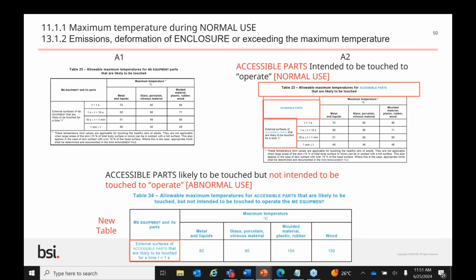Maintenance Team 30, the Overheating, Fire Protection, and Additional Hazards Maintenance Team, updated Table 23. So A1 is on the left at the top and A2 is on the right. This is for the normal use condition. That's not part of the title. Just below is the title. The title changed from A1, ME equipment parts that are likely to be touched, to A2, accessible parts that are likely to be touched. And we changed ME equipment to accessible parts in 3 places in the red boxes where you see the blue writing.